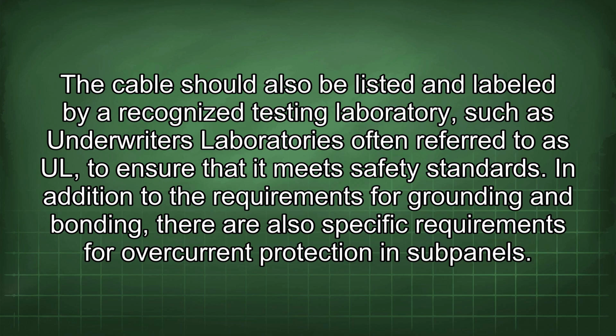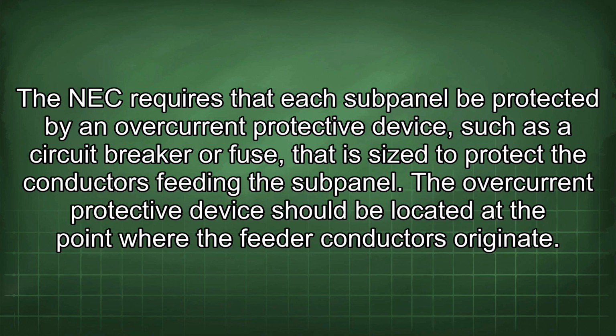In addition to the requirements for grounding and bonding, there are also specific requirements for overcurrent protection in subpanels. The NEC requires that each subpanel be protected by an overcurrent protective device, such as a circuit breaker or fuse, that is sized to protect the conductors feeding the subpanel. The overcurrent protective device should be located at the point where the feeder conductors originate.